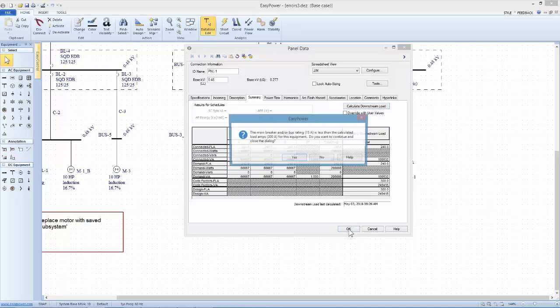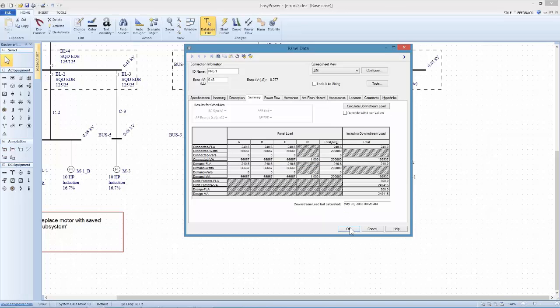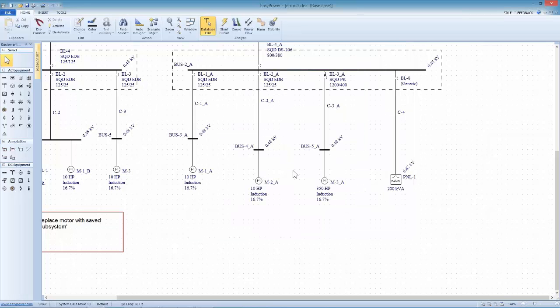Then as I try to close it, if I've made a mistake here, and it looks like I have, I set my main breaker up for a 15 amp setting, and yet the loads in the equipment show 300 amps. So there's clearly a disconnect here, and the tool's trying to give me a chance to redeem myself. So again, pay heed as these kinds of mistakes are noted.